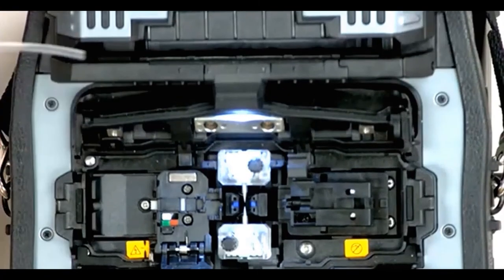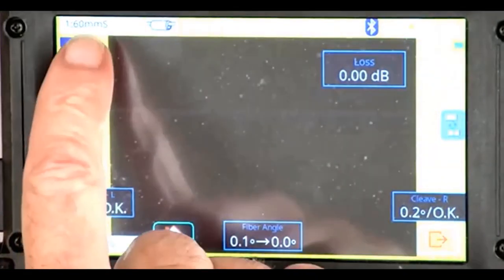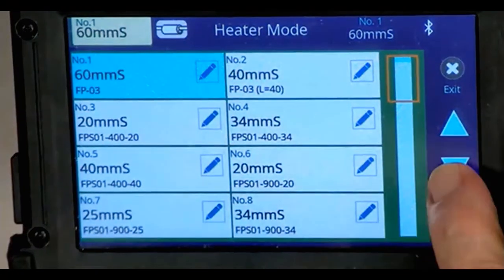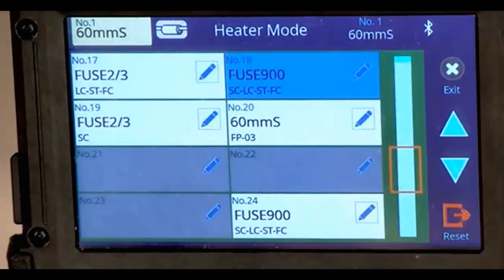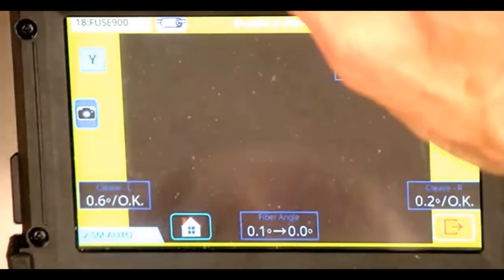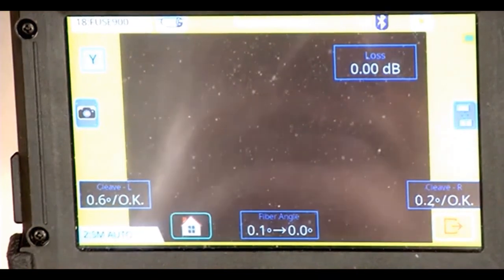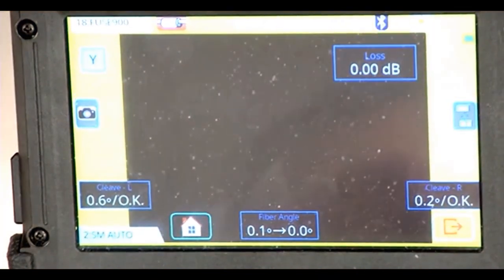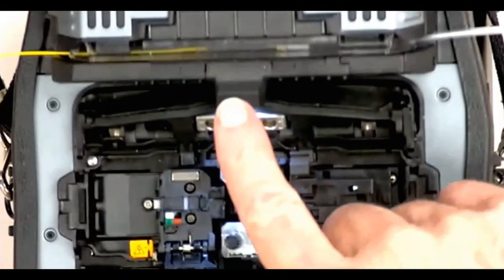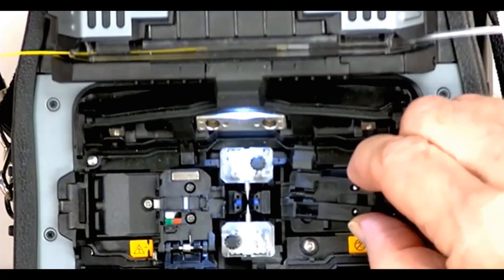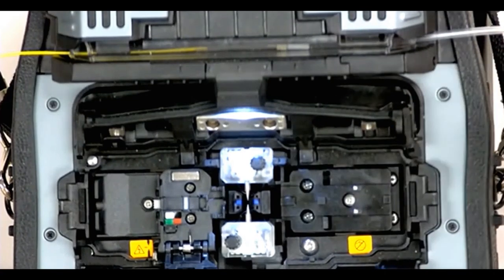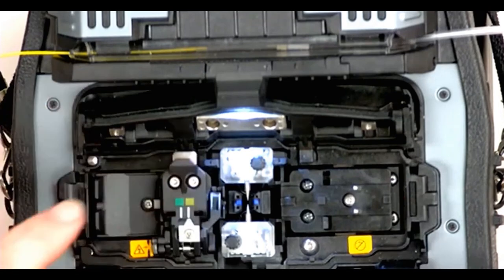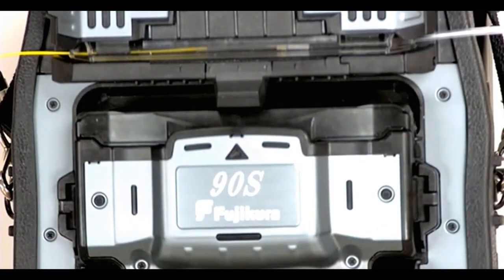Now, right now, I am not in the proper heating mode. I'm in the mode for a 60 millimeter sleeve. So let me go in here, put it on this one, and now I'm ready to do the heat shrink process. And it's already closed and is heating. At this point, I can pull this out and throw it away, because it's a disposable temporary holder, and I'm ready to start my next process. While that is heat shrinking down, I'm going to talk a little bit about what's different about 2 and 3 millimeter.